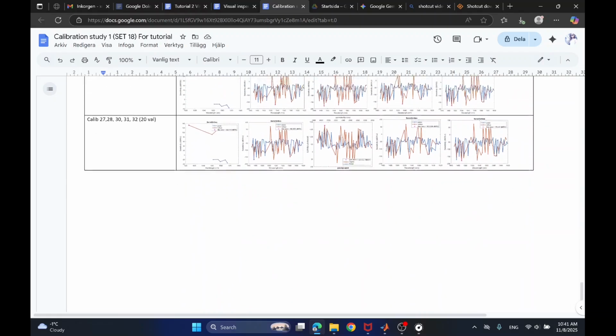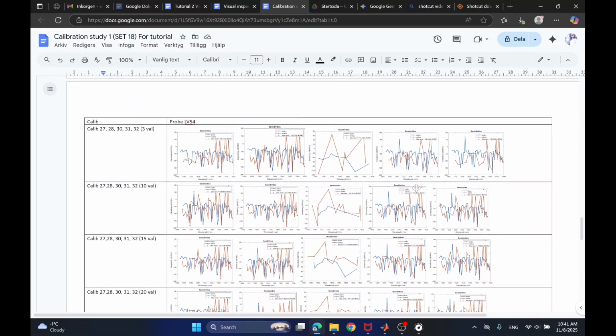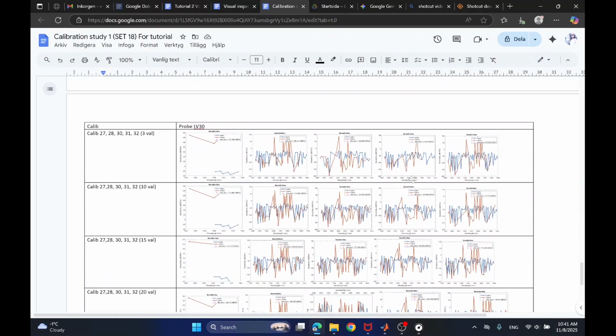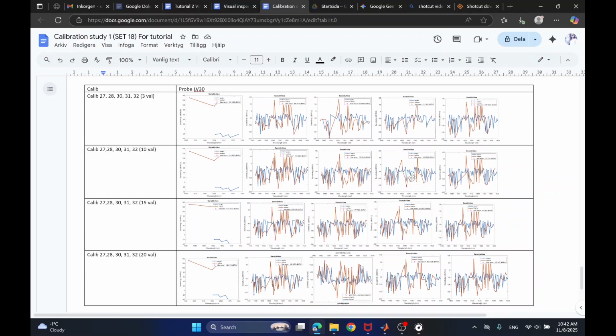I did not make any statistics on this, but you see that the chances are not zero, and it's better not to take chances by discarding a probe without second consideration. We will focus on the story of the probe with codename LV30, which is the most dramatic one. As you can see, the first calibration was a mess, and I would have discarded this probe. But fortunately, it was part of the calibration stability study and got rescued to show very good sensitivity afterwards.